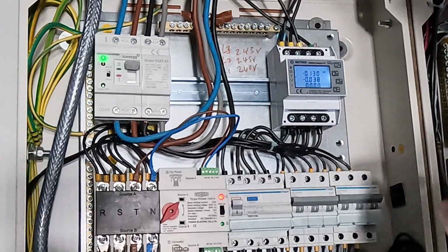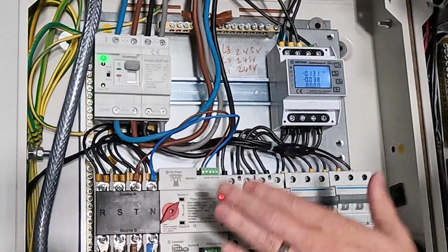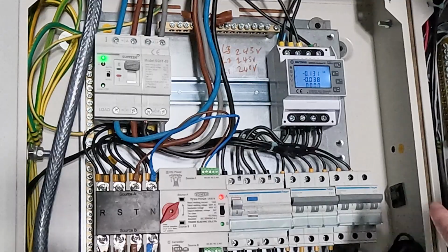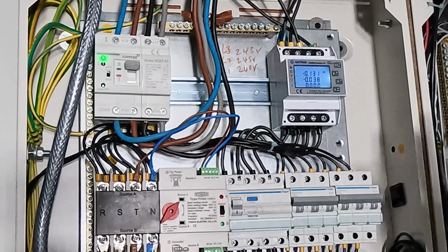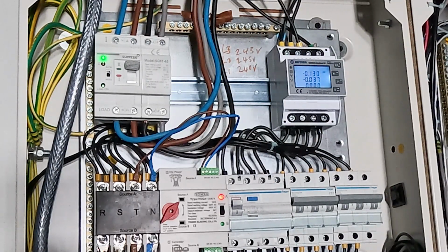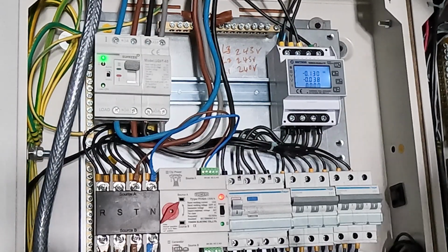So it was a fast enough transfer, and this is when the inverter did the transfer. That was a 20 millisecond off time, which kept that up and would have kept up desktop computers, televisions, all those types of loads. Resistive loads wouldn't even notice it. Your LED lights, you might see a flicker. Our eyes can detect 60 hertz, and your fluorescents will do their thing, obviously.